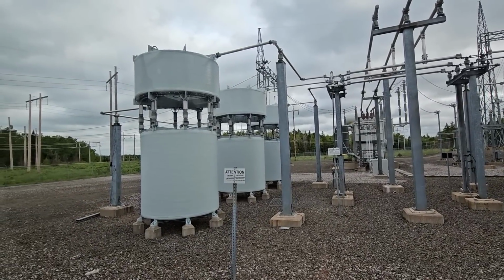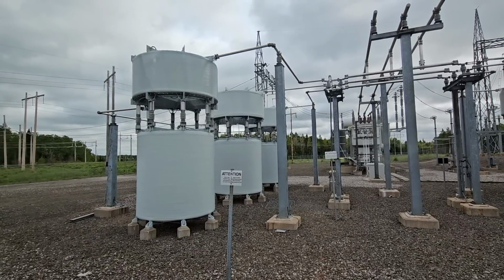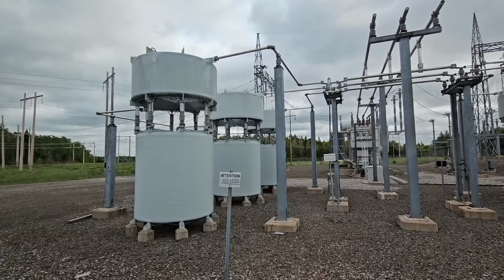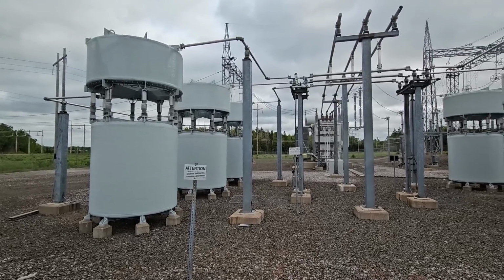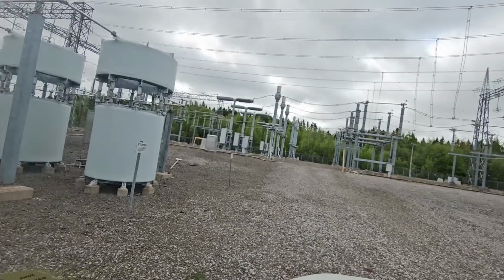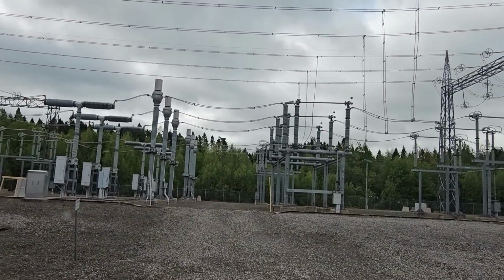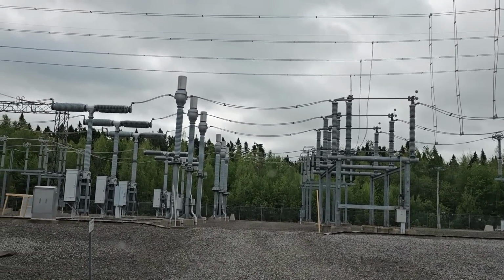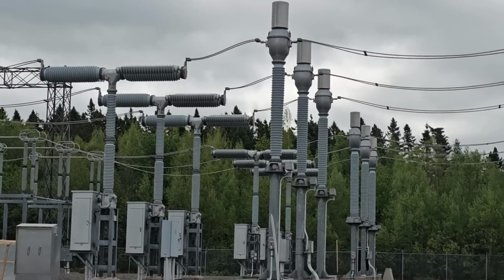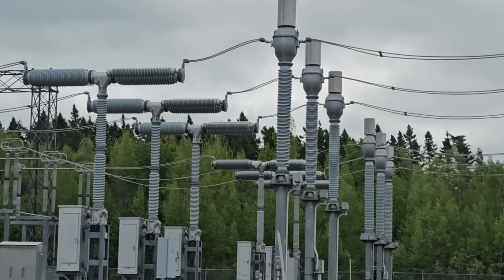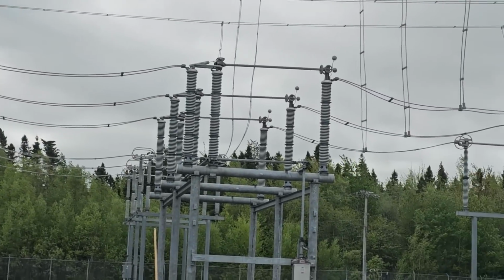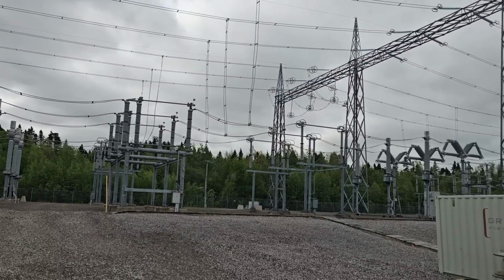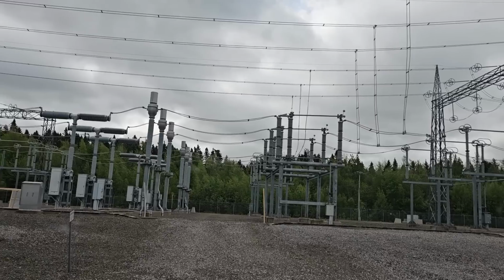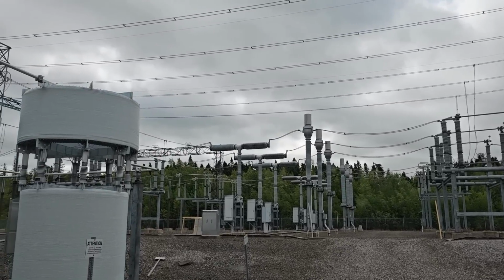Well, they're energized at 12,000 or 7,200 volts phase to ground on a 12 kV system, but that's tied into our 345 kV yard. That's our 345 kV yard over here. Those are the air breakers for the 345 kV. Pretty interesting stuff. I always like coming to the terminal yards to do switching. Not something we specialize in as linemen. We do have substation techs.